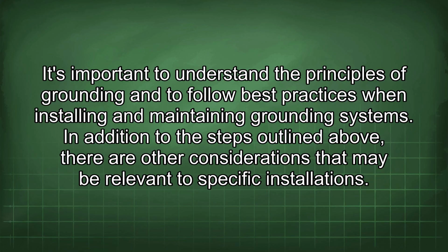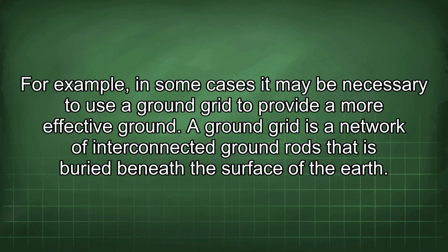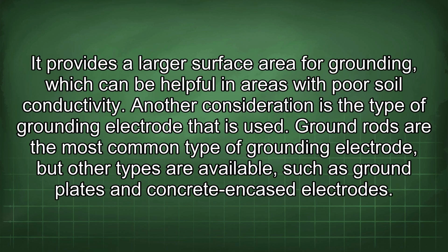In addition to the steps outlined above, there are other considerations that may be relevant to specific installations. For example, in some cases, it may be necessary to use a ground grid to provide a more effective ground. A ground grid is a network of interconnected ground rods that is buried beneath the surface of the earth. It provides a larger surface area for grounding, which can be helpful in areas with poor soil conductivity.